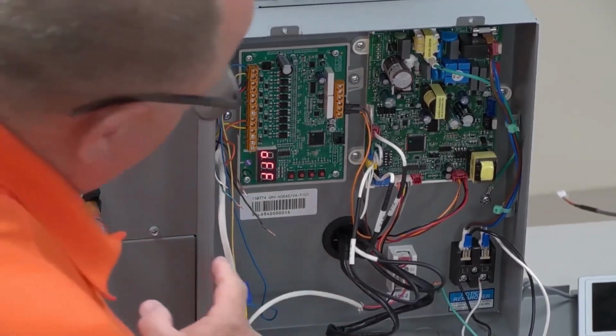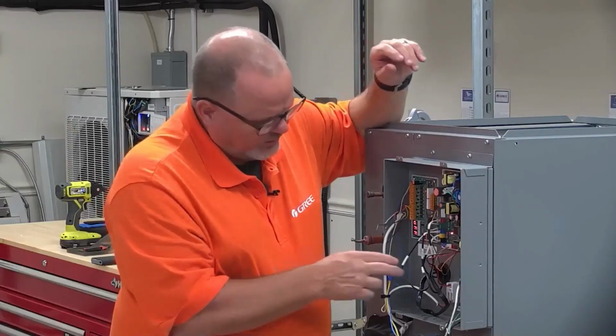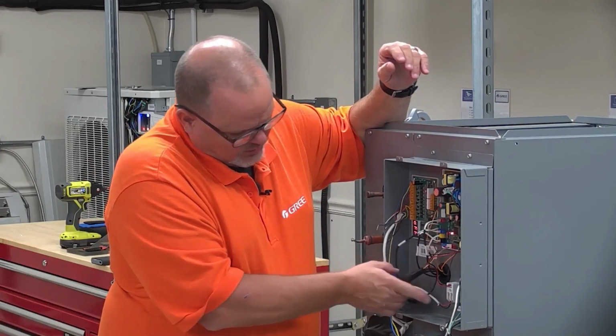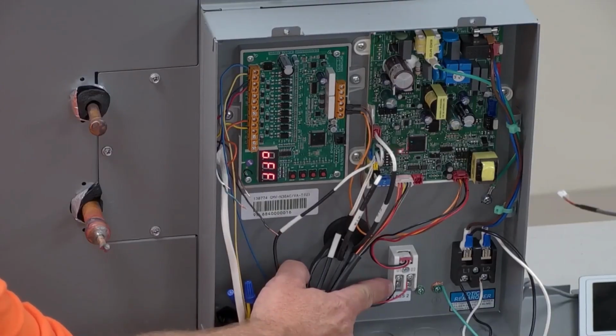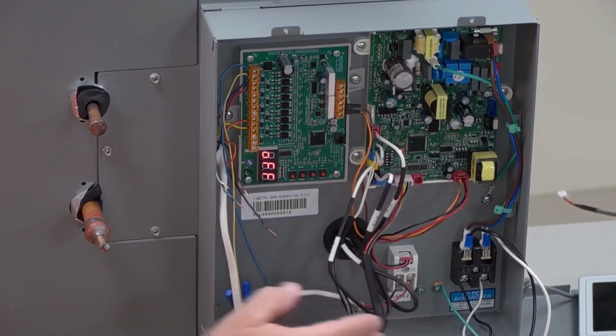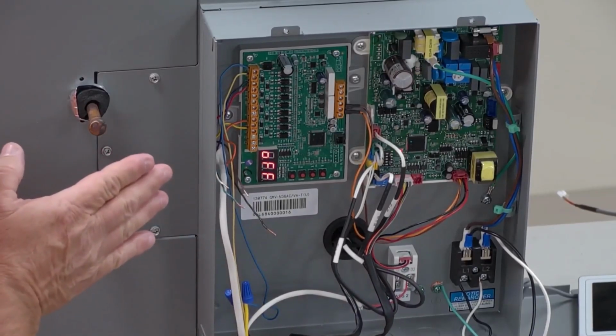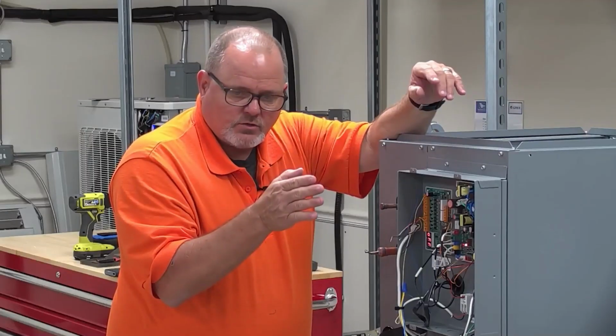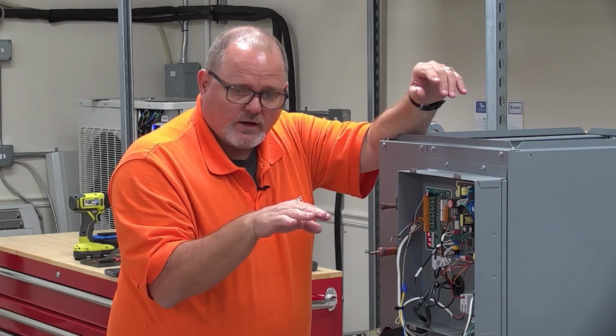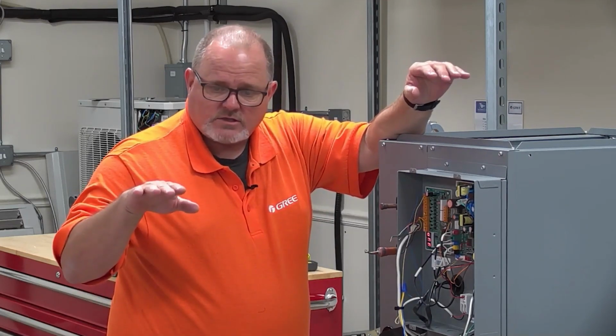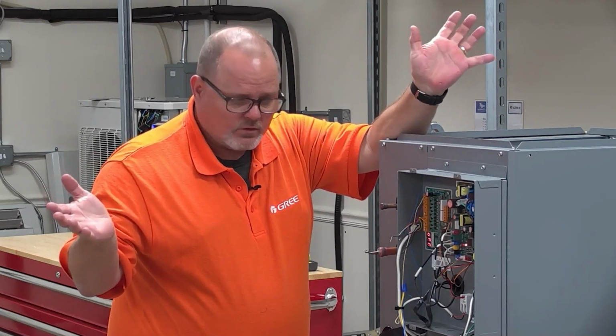And then you're going to have your D1 and D2 connection right here. That D1 and D2 connection is going to go out to your outdoor unit in that daisy chain fashion, just like we've done with MultiPRO before. Remember, from the outdoor unit, you got a D1 and a D2. It goes to the first indoor unit. It goes to D1 and D2 there. It daisy chains to the next indoor unit until you run out of indoor units, however many you have.